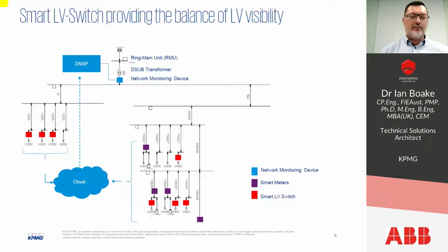So you can see on every installation on this particular network, there is a smart meter where there's PV or DER behind the meter. What I'm proposing here is to use these LV smart switches to provide the rest of the visibility, and for that information to be shared via a cloud and a shared API key with the DNSP at no charge. That is of benefit to both the consumer for their energy management and controlling their loads, but also for the DNSP to get that visibility in order to provision better hosting capacity, and for the aggregator to orchestrate the best possible value from that DER.